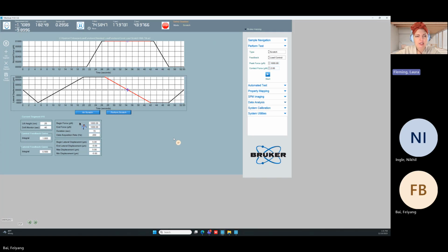decrease this force drastically. So the problem with scratch training with a Berkovich probe is that we run the risk of blunting your probe. So for the purposes of training, I typically do very, very light scratches to prevent damage. So let's change that peak force to 200 micronewtons. Perfect. And you can see now how this is updated.